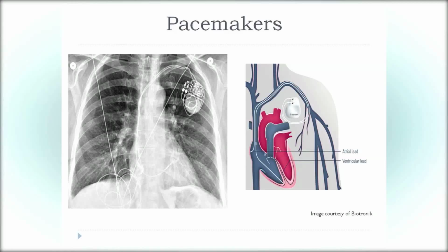This is the diaphragm. So rarely, if somebody has a twitch, if they've got what's called a biventricular device, it'll be pacing the diaphragm. It's close enough. This lead is not even close, but the phrenic nerve, which paces the diaphragm, comes here. And sometimes we can be twitching the diaphragm. They're going like this. They get irritated in a hurry. So we always test for that.